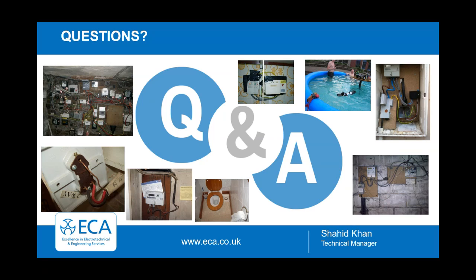The ESF best practice guide typically raises that as a C3, but if there's any signs of heat damage, the breakers being jimmied in, then yeah, absolutely knock it up to a C2 at any point. The little slide Shahid showed with the decision tree was very pertinent, because there was a question earlier on about ECA producing a guide similar to a code breakers book that some other organisation produced.